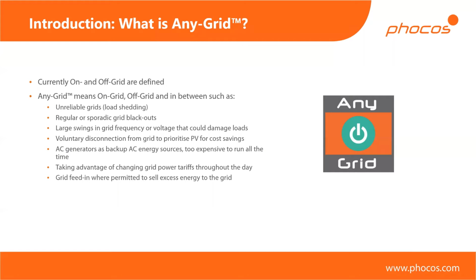Then we might have different types of AC generators. So this could be gensets of any kind, diesel, gasoline, could be a fuel cell, etc., where typically those energy sources are more expensive than PV, especially obviously once the investment has been made. So you want to have those as a backup energy source, but you don't necessarily want to have them running all the time. Because as you probably know, having a diesel or a gasoline generator running all the time at a very small load, like maybe at 5 or 10%, it's like idling your car. You're basically just wasting fuel most of the time. So it's much more interesting to just activate the generator when you really need it, to then use that to charge your batteries, and then to switch it off again so that you're using it in a much more fuel-efficient way.